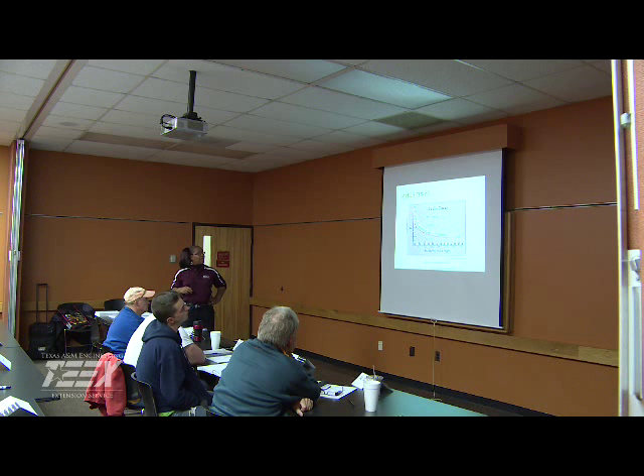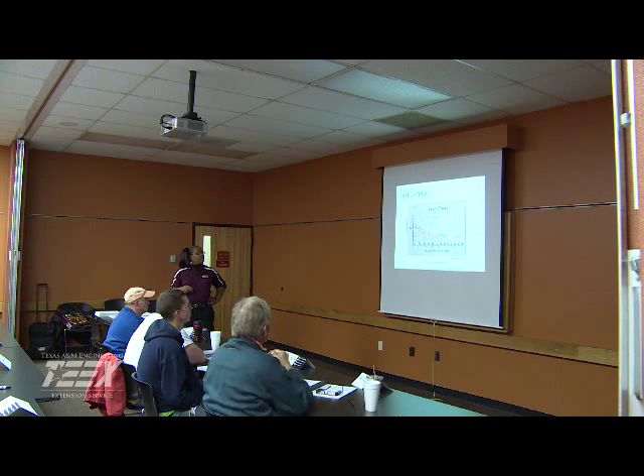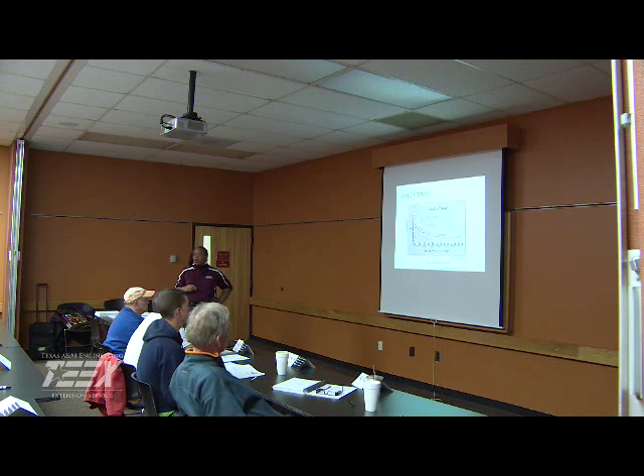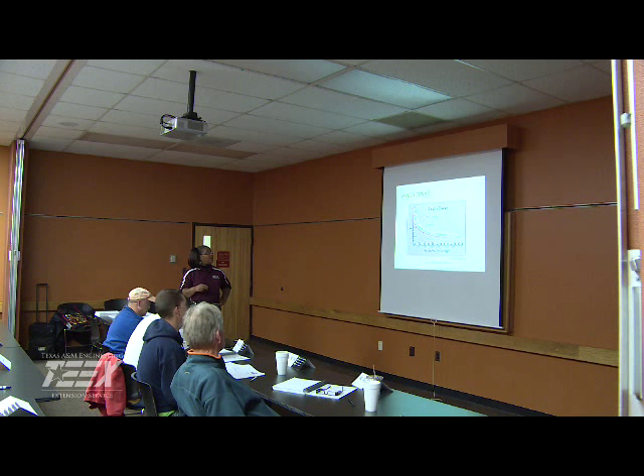Anything below the red line is corrosive. Anything above the yellow line is scale forming. Okay? And neither is good for our operation, so we want to be between the lines. The reason I was asking you about alkalinity earlier is that you mentioned the pH being way up here, adding chemicals, which tells me that your natural alkalinity was very, very low.